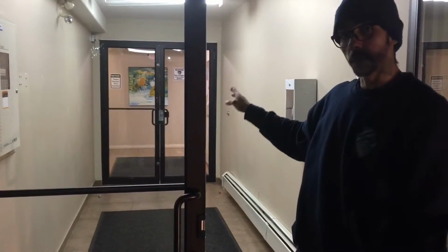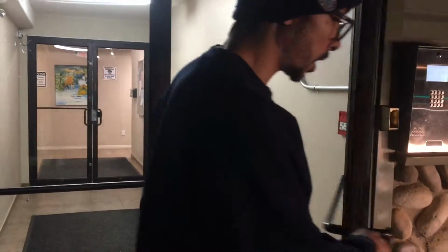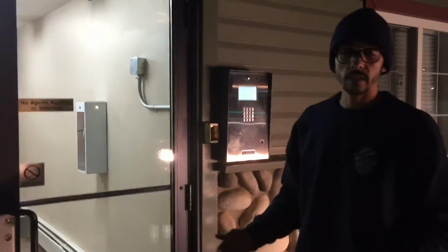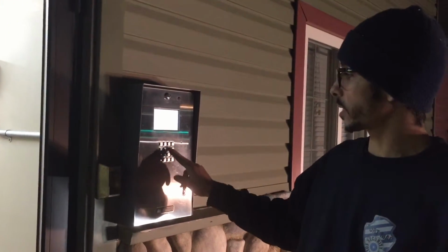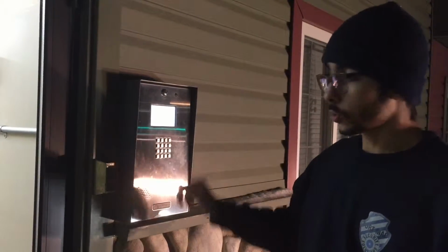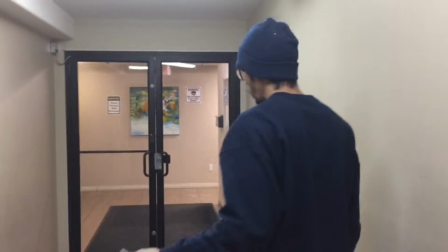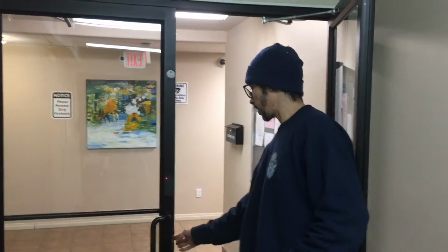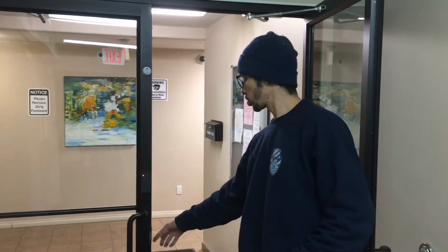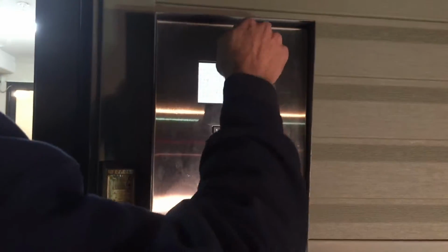For the other door, there's another reader, but for the intercom, if you have a guest coming over who doesn't have a fob to get in, we call them and they grant us access. When we do our programming, we have to program both doors to release at the same time. So if you follow me, we program these doors to unlock for 10 seconds. Here we're at the second door, and we have roughly 5 seconds. You see, we have 10 seconds after the access is granted, so we can come in, and the doors will lock automatically.